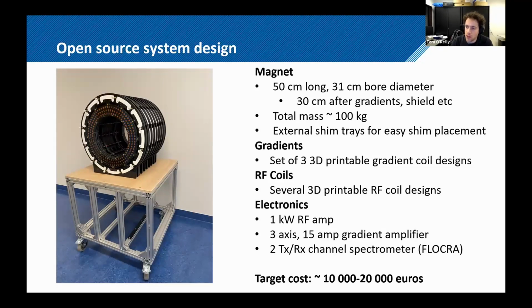It's based on a lot of the learning from the system that we had before. So again, it's a 50 centimeter long Halbach array. It's a little bit heavier because we made the bore 30 centimeters instead of 25 centimeters. But we'll provide all the drawings, the 3D print files for the gradient coils, for the RF coils, for the electronics. And we're looking at options where we would, for instance, order a batch of the electronics or order a batch of the materials needed to construct the magnet to help other groups set up their own system.